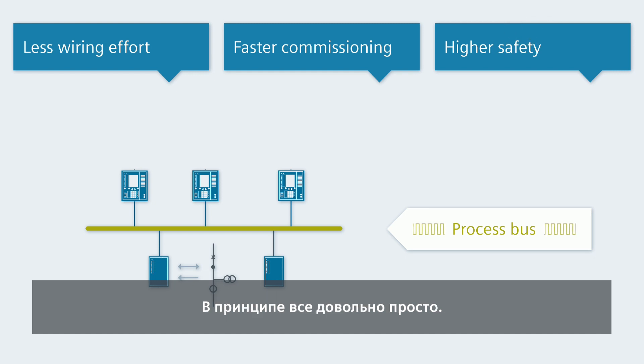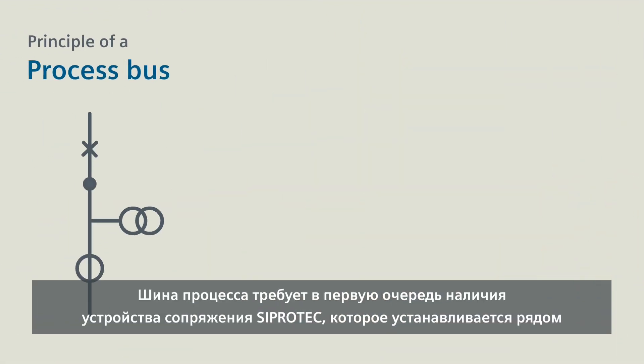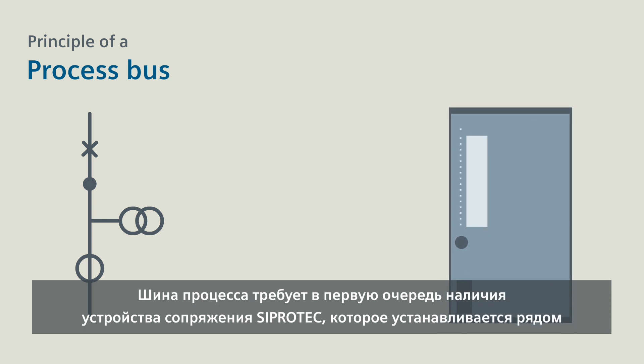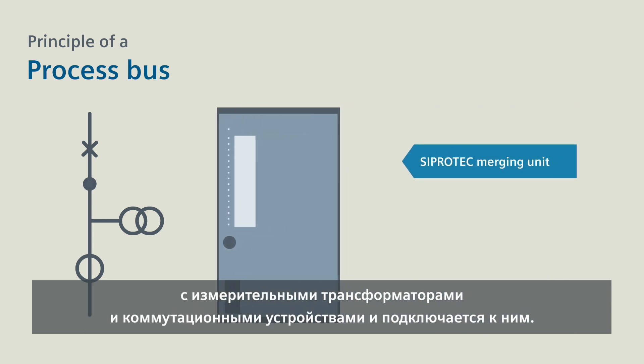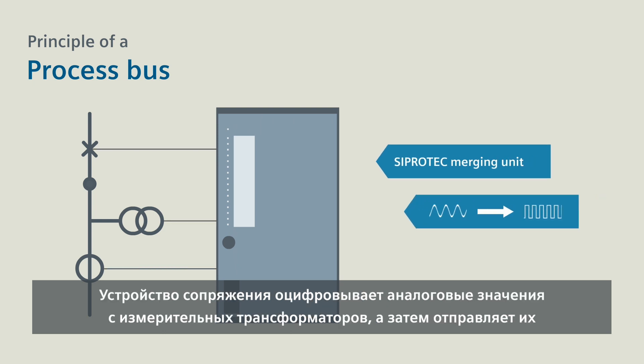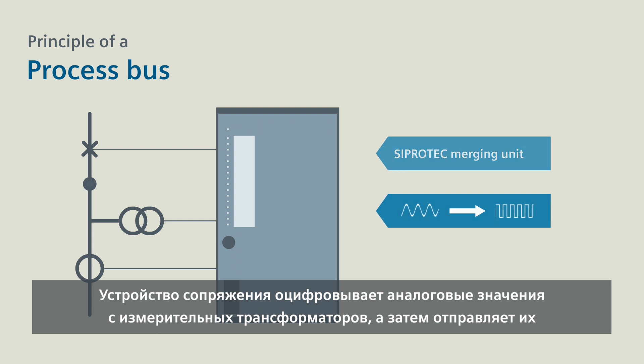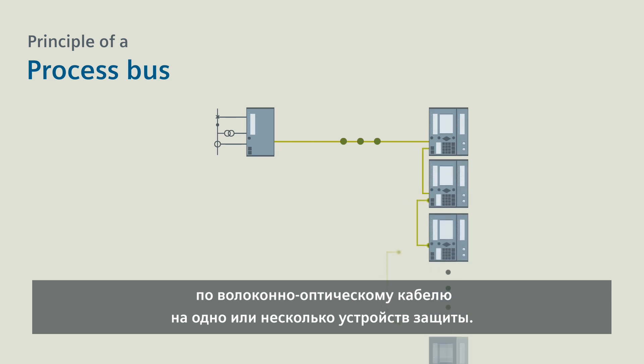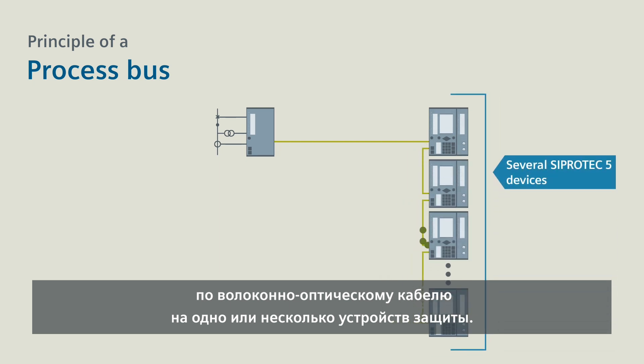In principle, everything is quite simple. For a process bus, you first of all need a SIPROTEC merging unit, which you place close to the instrument transformers and switching devices and connect it to them. The merging unit digitalizes the analog values of the transformers and then sends them via a fiber optic cable to one or more protection devices.